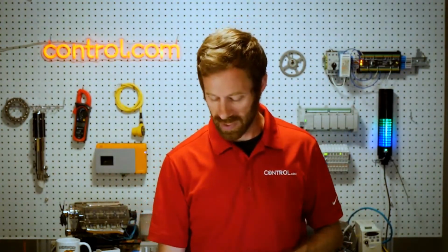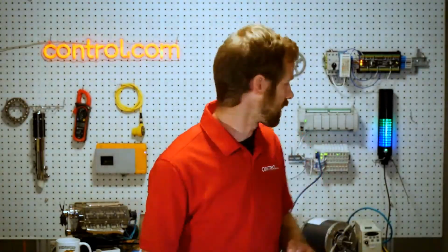Now, speaking of Modbus, that takes us to another kind of protocol, and it's a little bit of a variation from the last ones that we talked about. This one still is two-directional, but instead of the devices themselves connecting with this protocol, we're moving up a level, and this is what we'll find connecting between these hubs or remote I/O devices. Another example of a remote I/O device is behind me here. Between this and the PLC, sometimes some very unique applications and protocols take place.